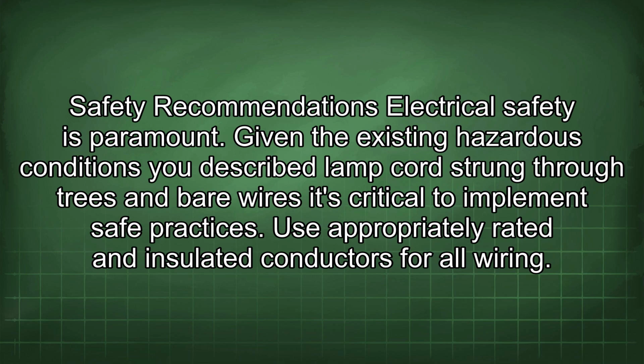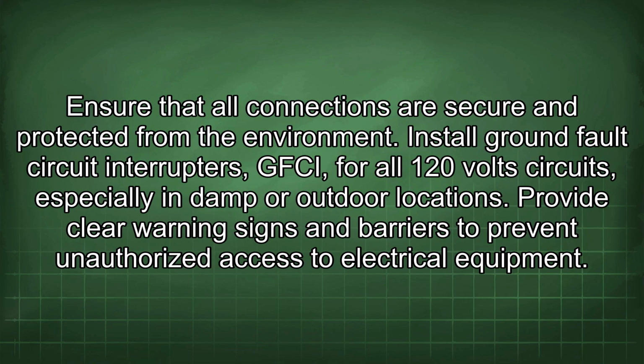Safety recommendations. Electrical safety is paramount. Given the existing hazardous conditions you described, lamp cords strung through trees and bare wires, it's critical to implement safe practices. Use appropriately rated and insulated conductors for all wiring. Ensure that all connections are secure and protected from the environment. Install ground fault circuit interrupters (GFCI) for all 120-volt circuits, especially in damp or outdoor locations.